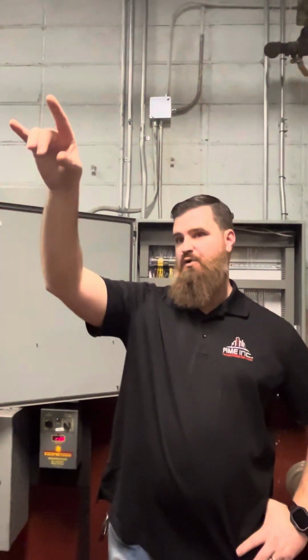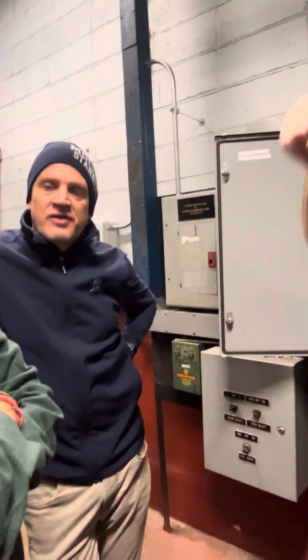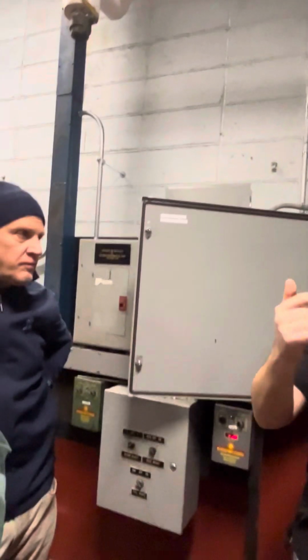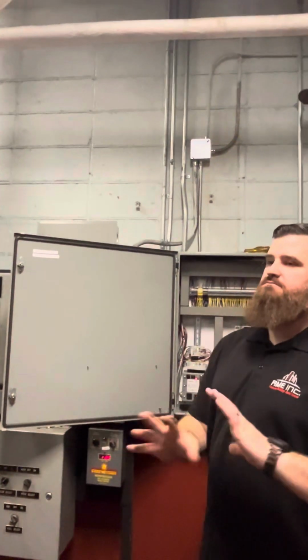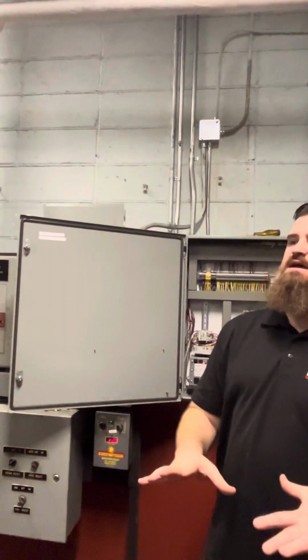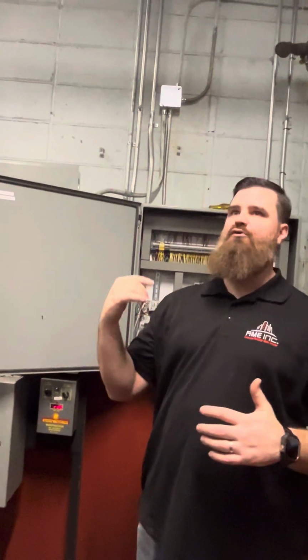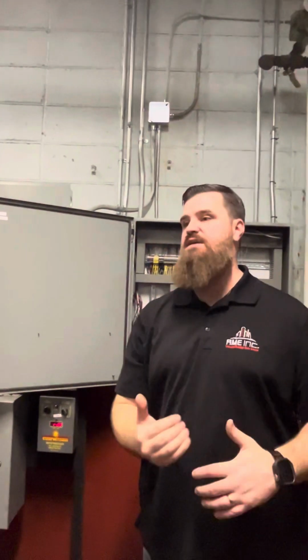I would not take control of those dampers on each boiler. They need to stay at each respective boiler. If you want us to go up there and monitor it, we can tie an end switch off it, something like that, so at least there's a panel over there. Again, just coming from a professional stance, it's a lot of liability for us if we take control of it. Secondly, if we want to fire that boiler, it's a lot of rework for us to, one, take control of that damper, and two, send a signal back to the boiler controller saying, hey, this damper's open.